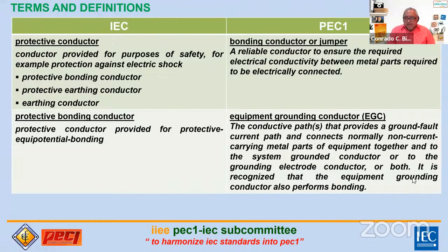It is recognized that the equipment grounding conductor also performs bonding, because it connects all the body parts, the exposed conductive parts, and routes back to the source. If you have a fault - ground fault, earth fault, or whatever - it goes back to the source, so that your protective device can monitor and sense this to trip. So this equipment grounding conductor, or IEC protective bonding conductor, is very important.